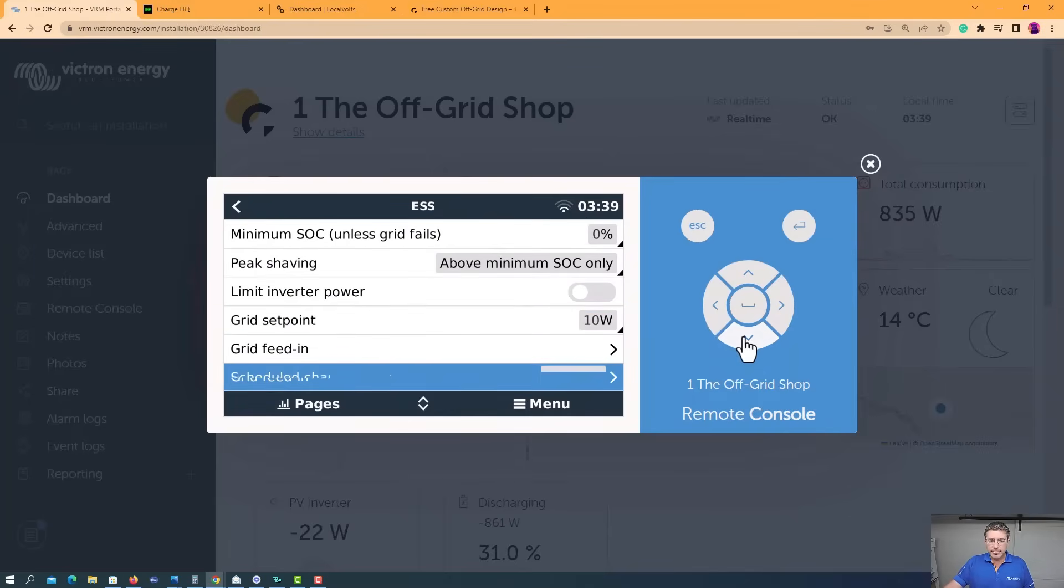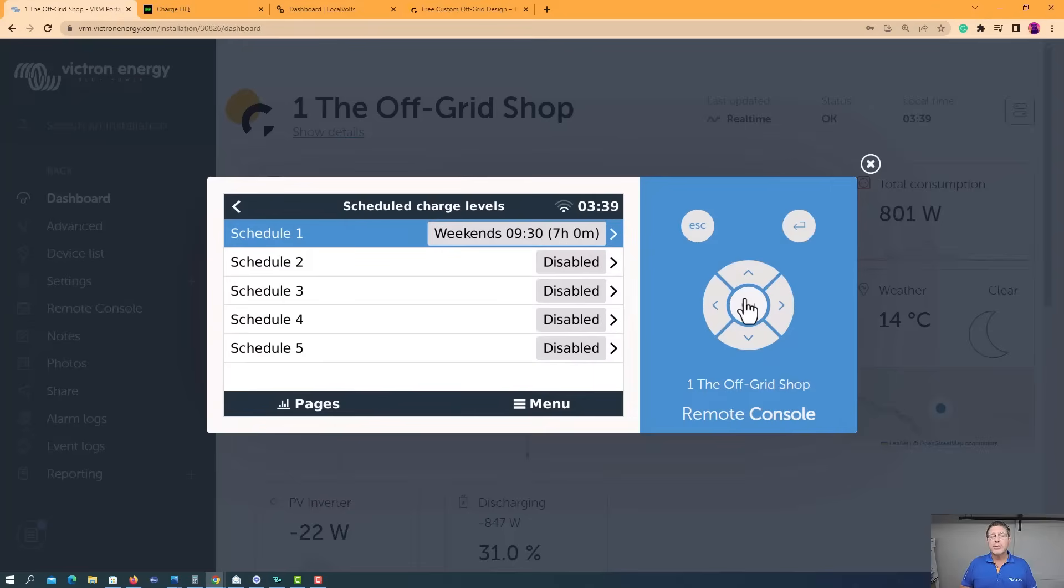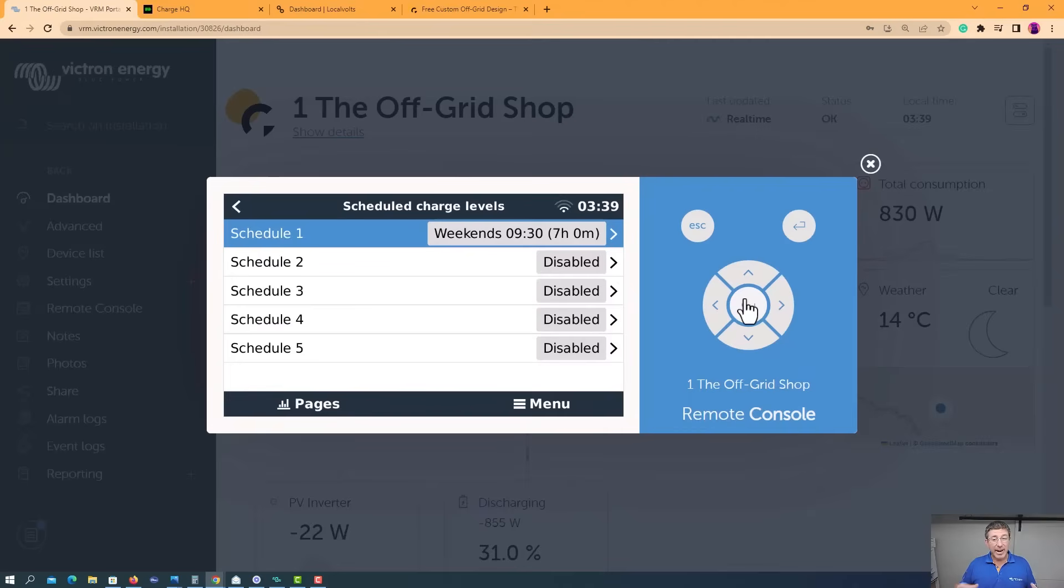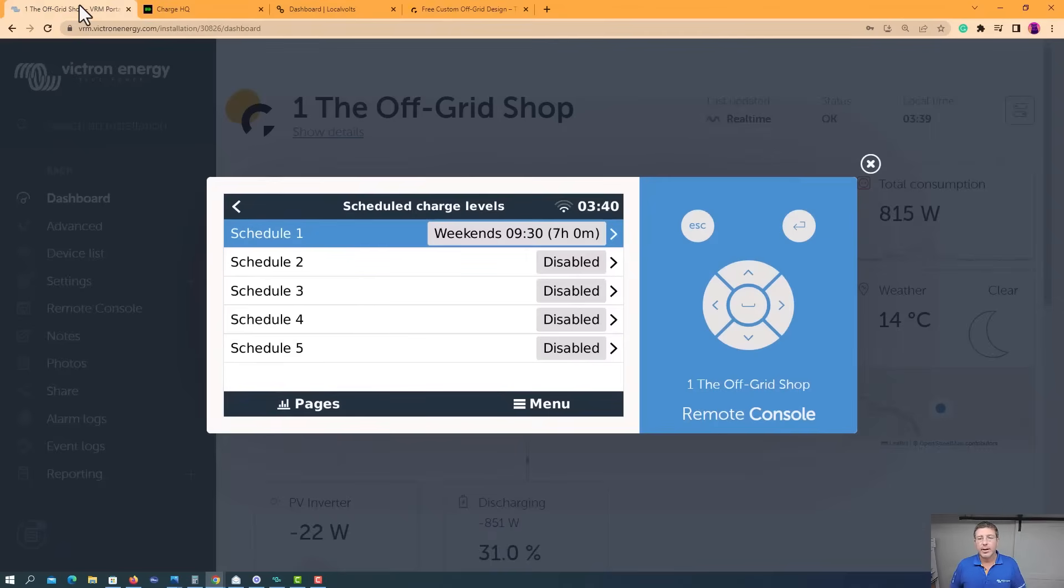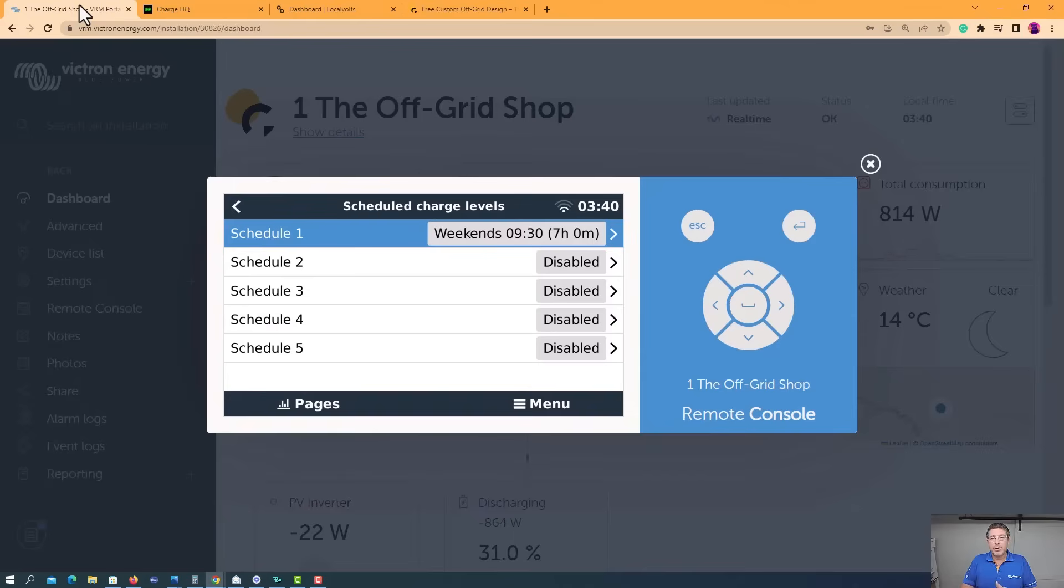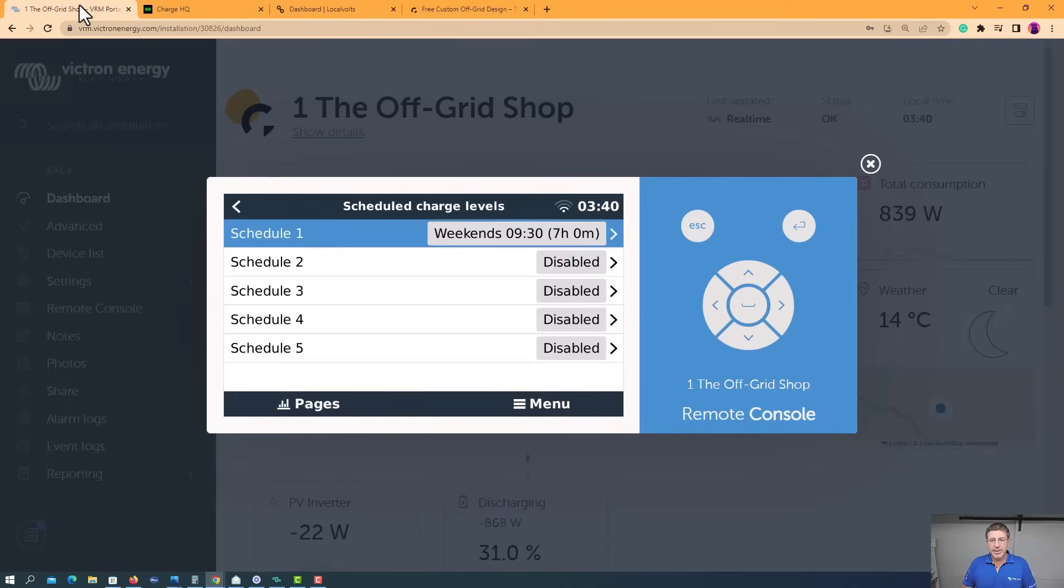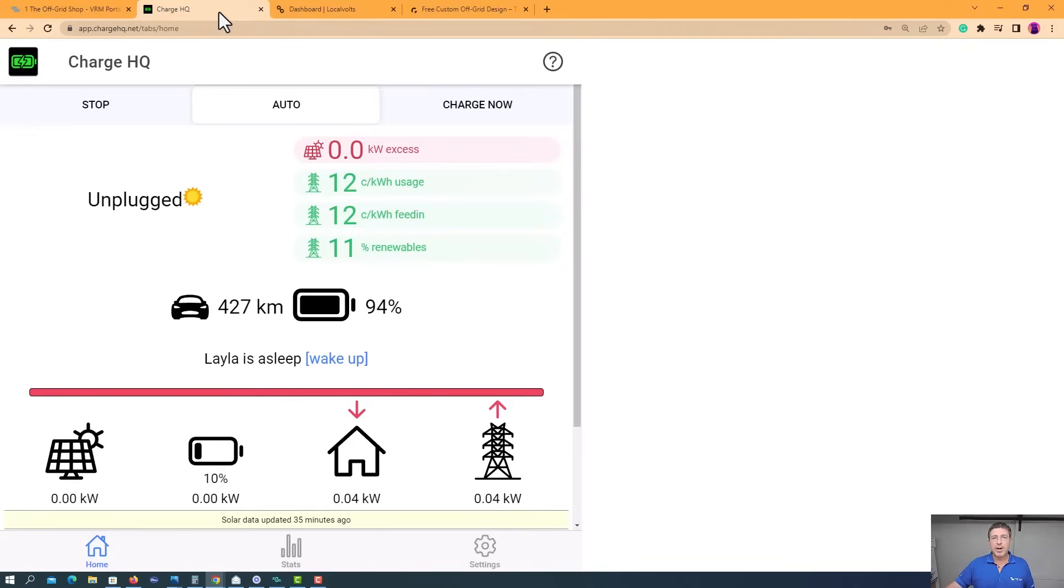Now we come down here, this minimum state of charge, this is where you can actually set it to 0%. For me, I've got two systems here, the way my house works. I run this system to 0% and then what happens, it goes over to another system. But this is here if you want to save your batteries and say, look, I want to keep 30% in there because if there is a grid failure, I want to make sure I've got power, I've got backup. And that's where this really comes down to what's really important for you and what you're trying to get out of the system. I'm not going to go into these, and come down to scheduled charging. So scheduled charge, if you're connected to the grid, how I use this, and I'll explain the reason I use it. So in Australia here, we have the wholesale energy market where the prices change and they fluctuate every five minutes. I'll show you right now. I'm on the wholesale market. It says I'm buying energy from the grid right now. I'm paying 12 cents a kilowatt hour.